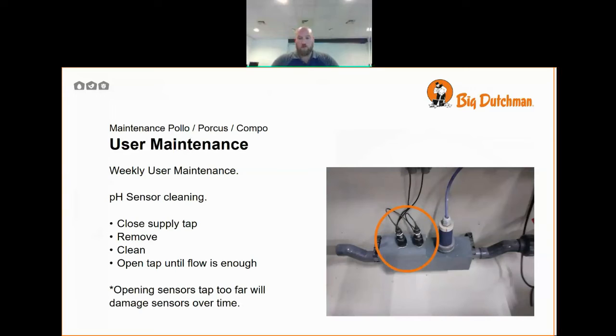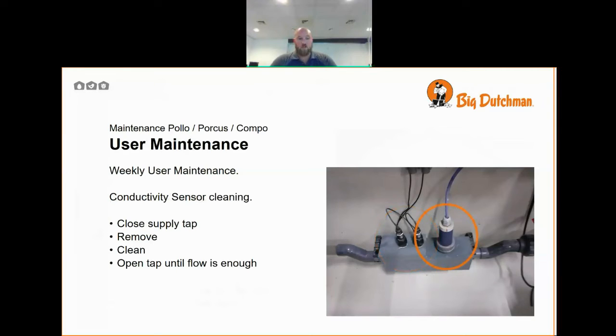Weekly user maintenance will include cleaning the pH sensors. So we close the supply tap to the sensor block, remove the sensors, clean them with a soft clean rag, reinstall them, and then open the tap until enough flow is showing on the sight glass to the left of the sensor block. Opening the tap too far will damage sensors over time and reduce the lifespan. pH sensors only have a lifespan of 12 months.